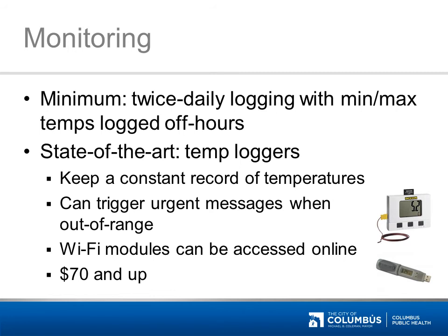In addition to having the right refrigeration unit, monitoring is important for vaccine safety. The minimum for monitoring vaccine temperature is to use a min-max thermometer to validate the highest and lowest temperatures since the last check. The temperature and min-max should be logged twice daily.